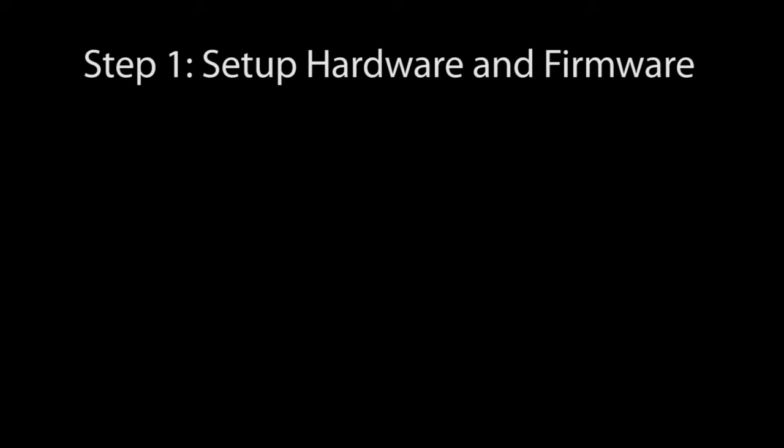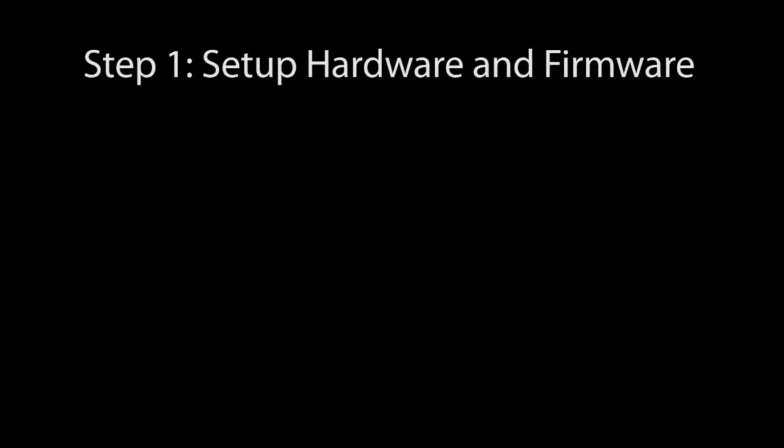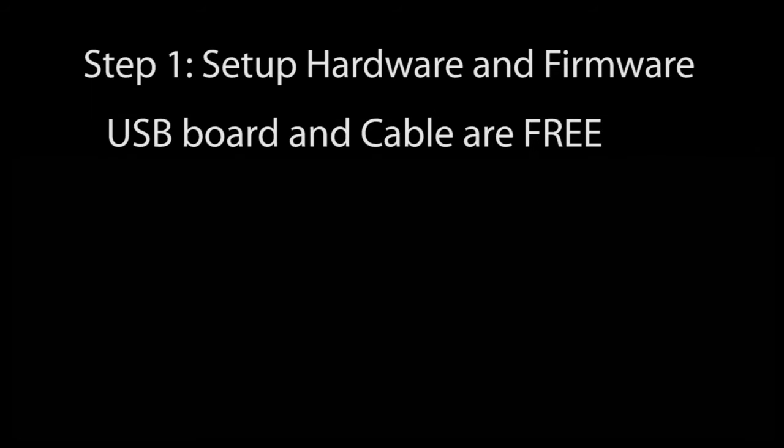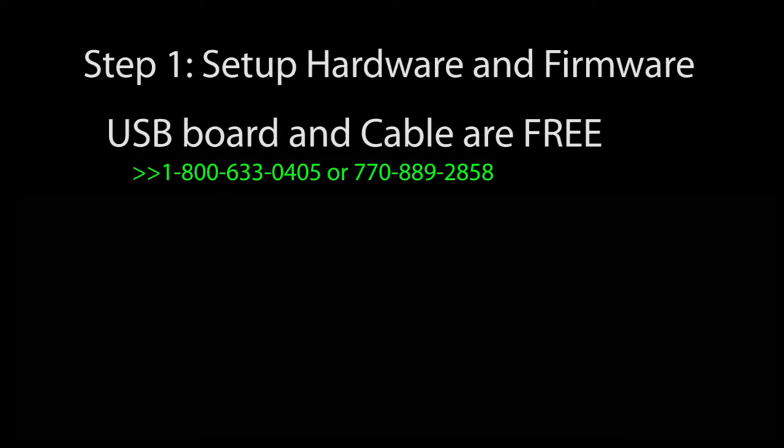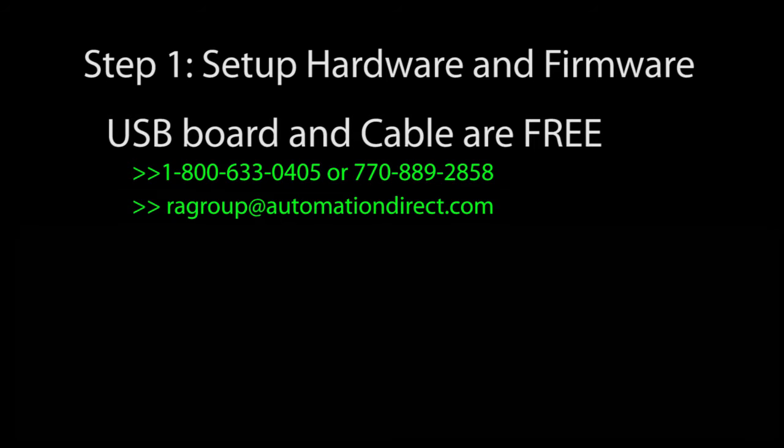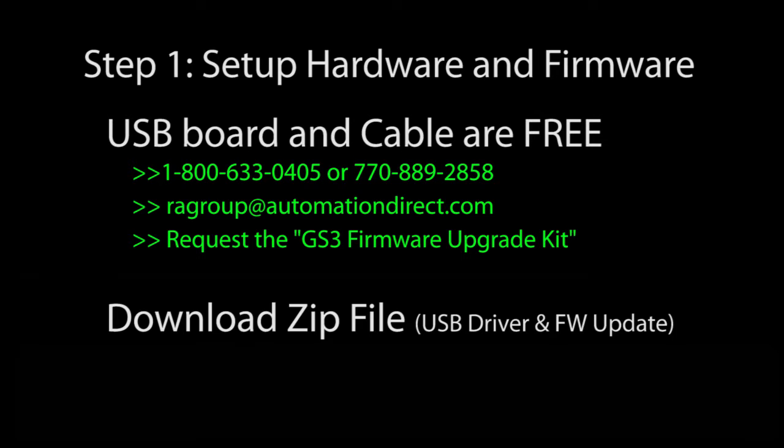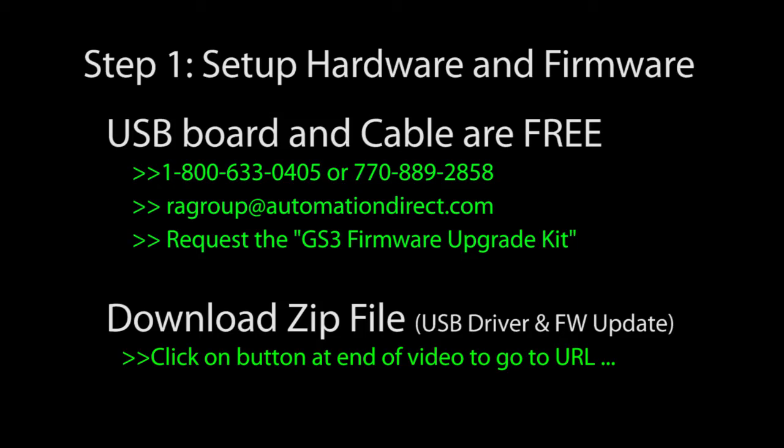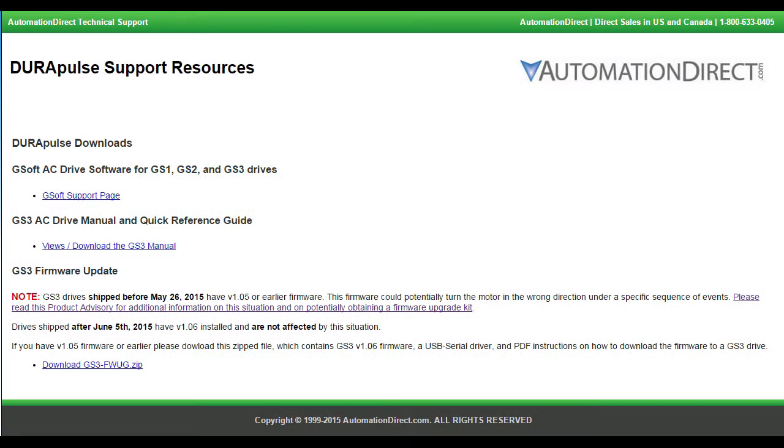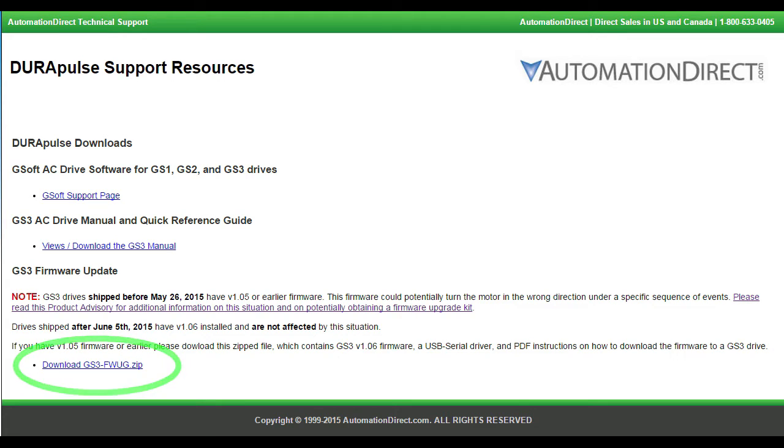Here we go. Step 1 Set up the hardware and firmware. The firmware upgrade board and the USB cable are free. Contact AutomationDirect's returns department and request the GS3 firmware upgrade kit. Download the file with the USB driver and firmware update. If you click on the button at the end of this video, it will take you right to this webpage so you can download this file. It has everything you need to do the upgrade – the firmware update and the driver for that USB adapter board.